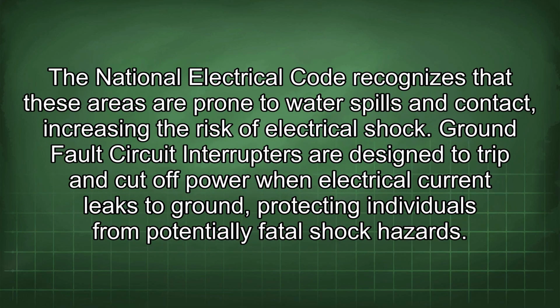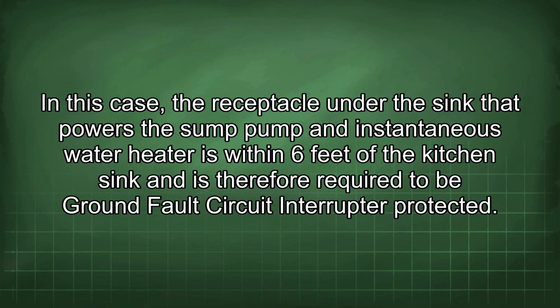The National Electrical Code recognizes that these areas are prone to water spills and contact, increasing the risk of electrical shock. Ground fault circuit interrupters are designed to trip and cut off power when electrical current leaks to ground, protecting individuals from potentially fatal shock hazards. In this case, the receptacle under the sink that powers the sump pump and instantaneous water heater is within 6 feet of the kitchen sink and is therefore required to be ground fault circuit interrupter protected.